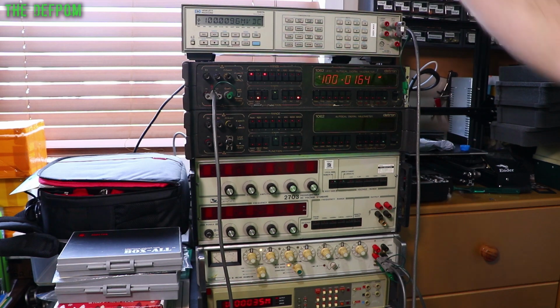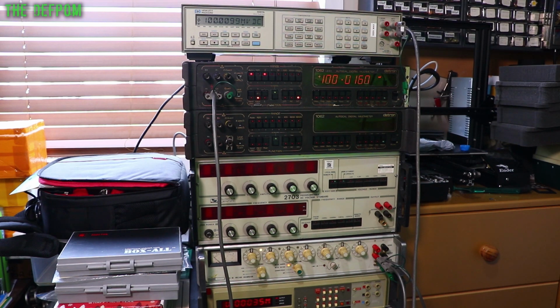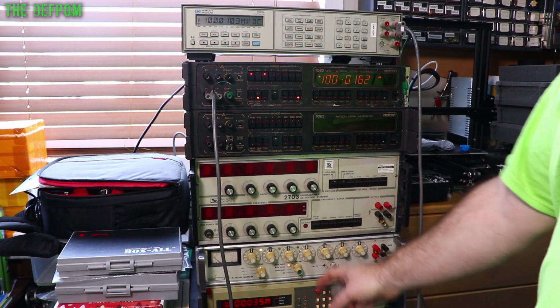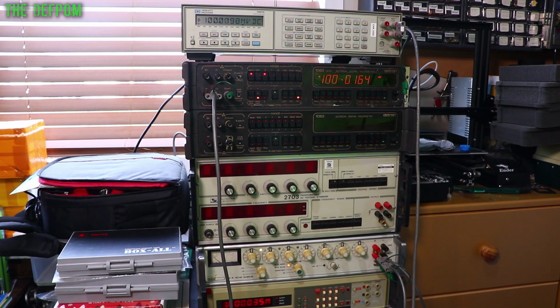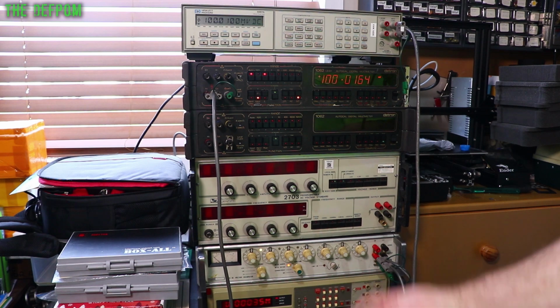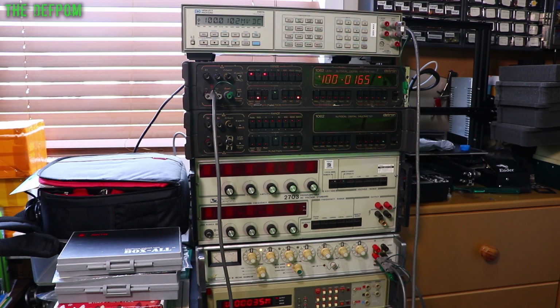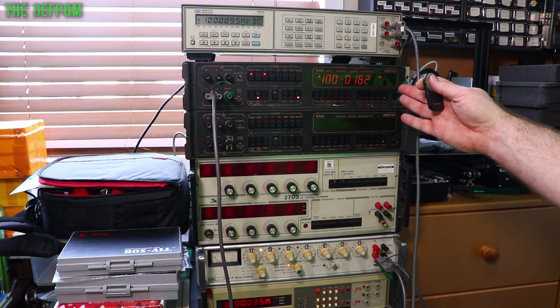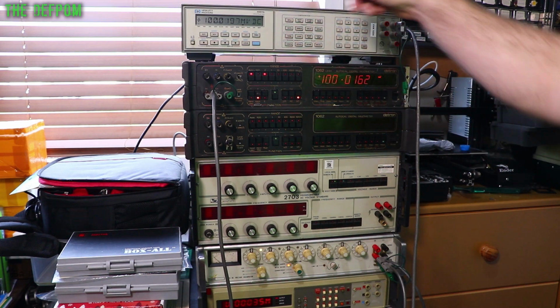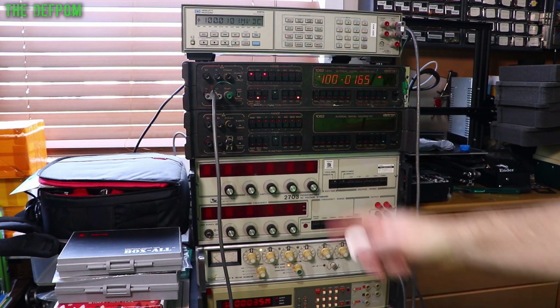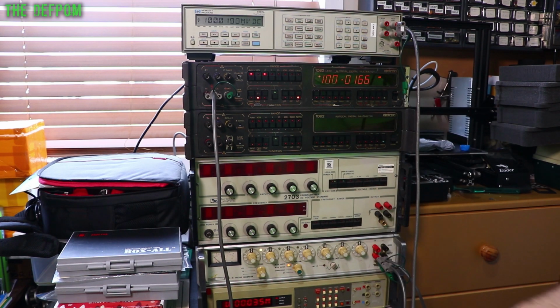But because this 10 megohm one has drifted off so much, I'm going to use my Fluke to provide a 10 megohm reference and stick a capacitor directly across the inputs, and hopefully that'll be good enough. We'll see what we get. I'll do it that way instead. Probably a bit less ideal, but that's what I'm going to do. So I need to start off with doing these shunts across here to actually calibrate the linearity. I'll show you the manual in a second.